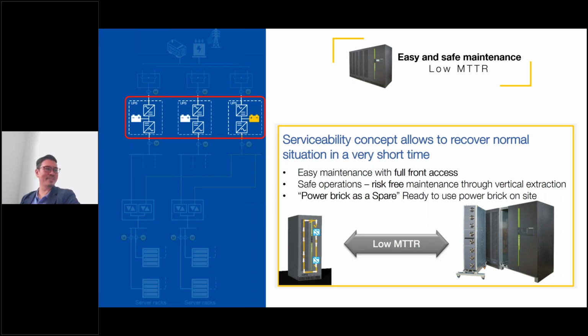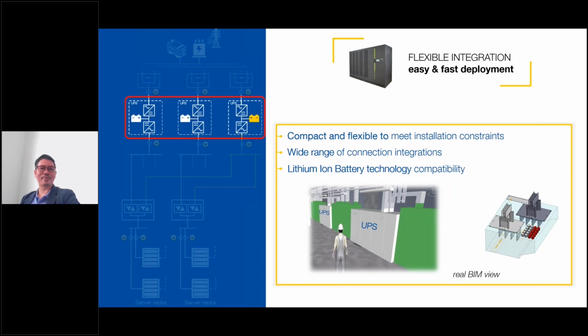Another benefit of full access is flexibility in cable wiring. I've seen UPS systems evolve over the years in this industry, getting smaller and more efficient. But how small can we really go? It comes down to the cabling and bus bar. What we need is the capability and flexibility to connect different types of electrical connections, whether bus bar or cables, top cabling entry or bottom cabling entry, and integration with other connections like bus bar plunges.